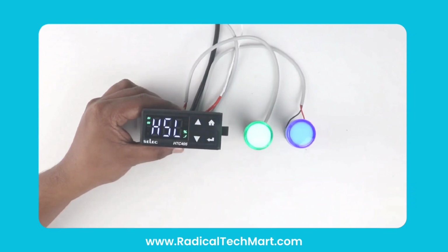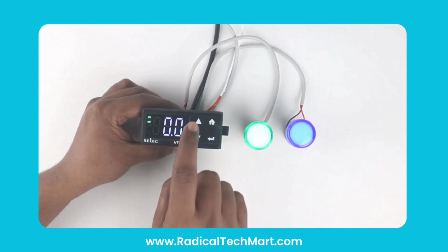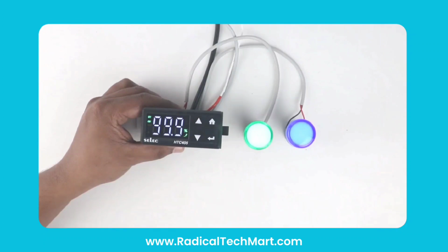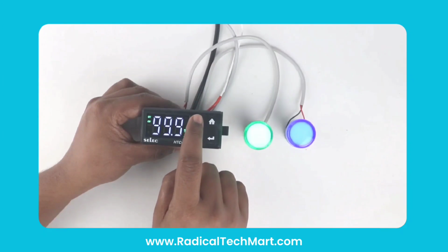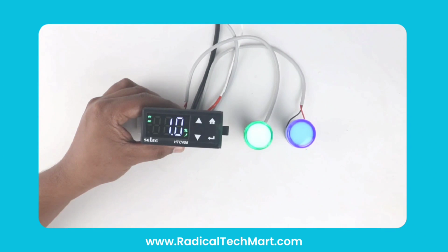After that, the humidity set point low limit appears. This is the lowest humidity value you can set on the main display. Similarly, the next parameter is the humidity high set point, which is the maximum humidity value you can set on the main display. The next parameter is the humidity filter time constant. It is recommended to keep this at the default setting.